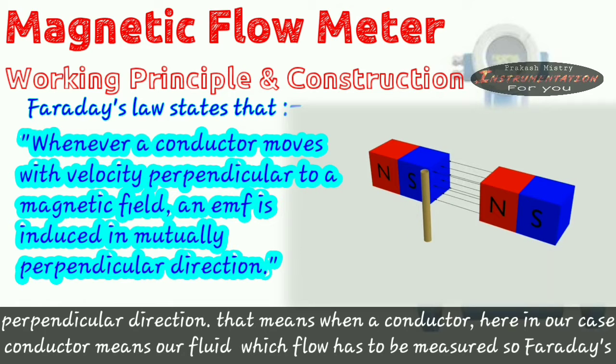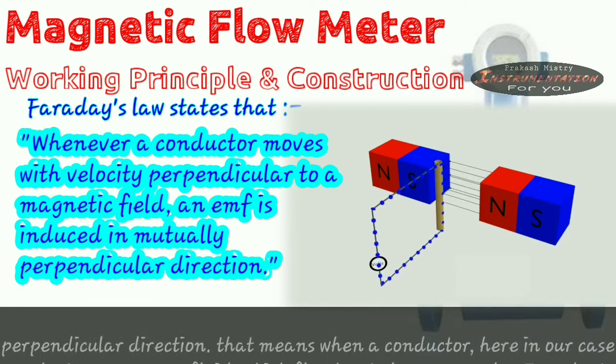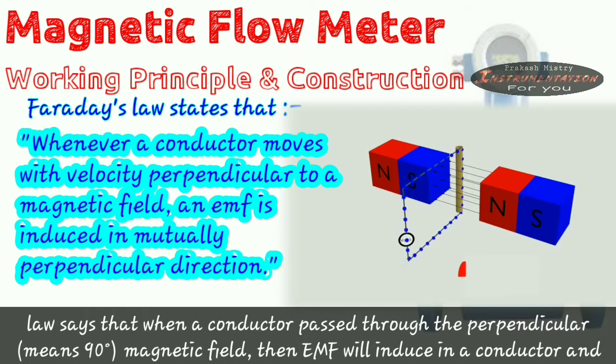That means when a conductor, here in our case conductor means the fluids which flow has to be measured. So Faraday's law says that when a conductor passes through a perpendicular, 90 degree magnetic field, then EMF will be induced in the conductor.